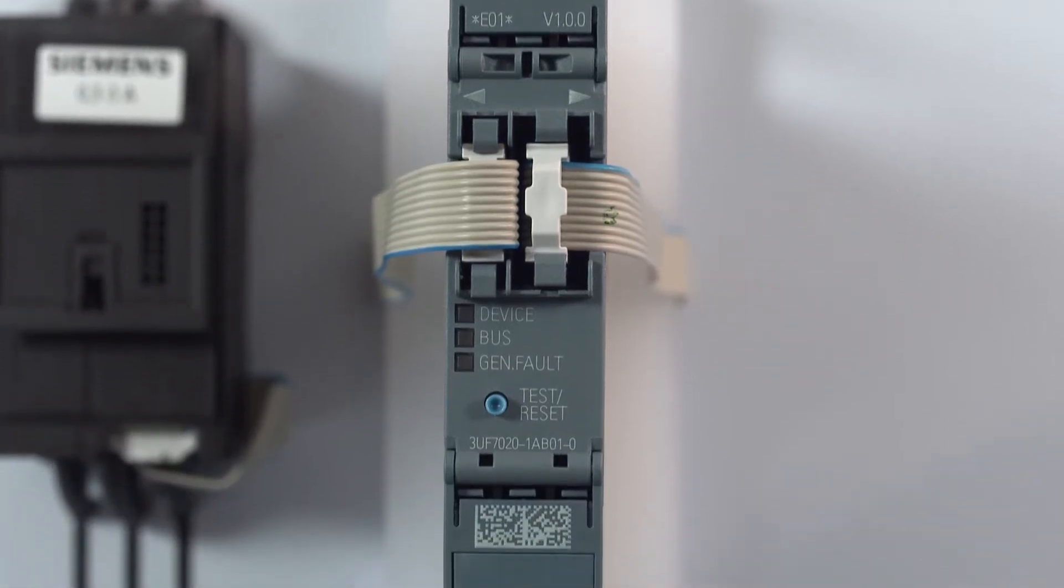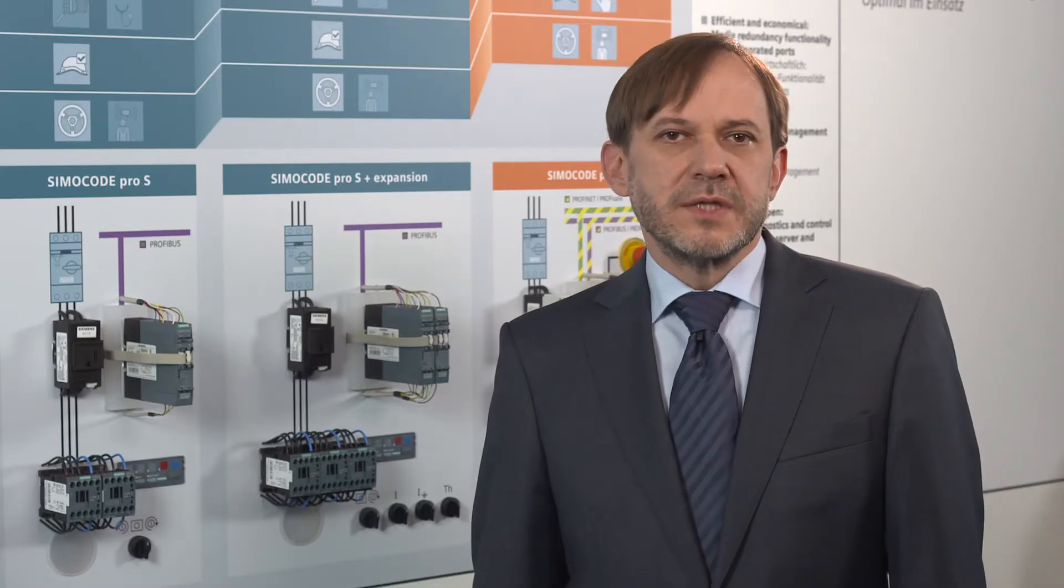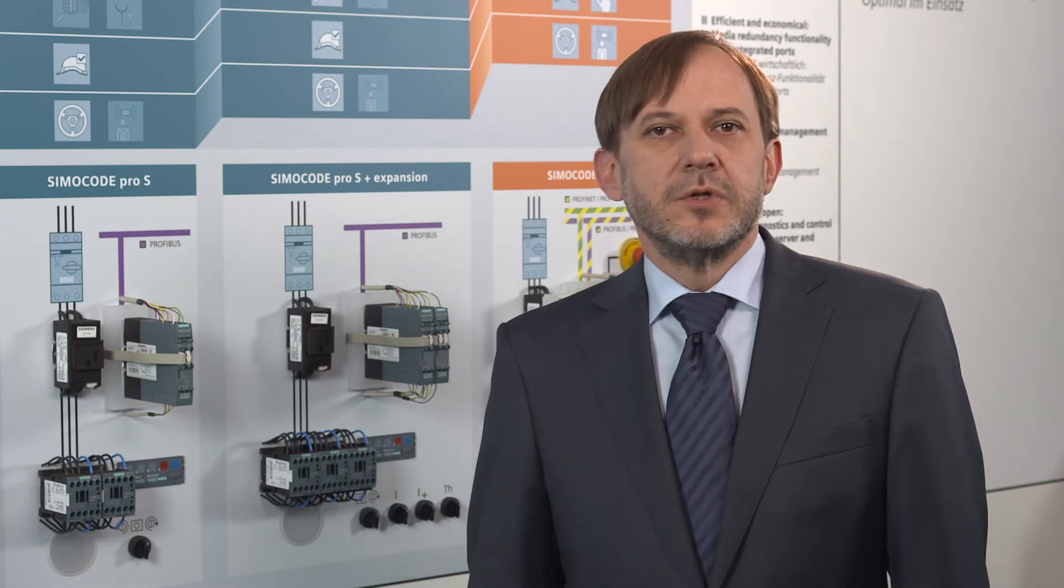As well as simple control functions such as direct online starting and reversing starting, it offers protection functions such as thermistor and overload. It has four digital inputs and two relay outputs and it monitors current limits, operating data and plant conditions.